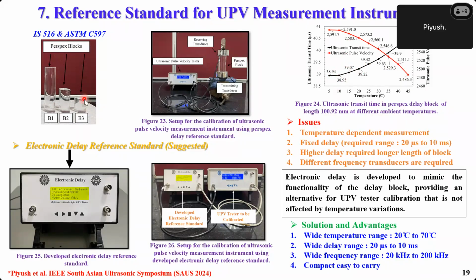Also, this small one, B3, is only for the 25 microsecond measurement, but the standard says we require blocks from 20 microseconds to 10 milliseconds. And this big one, B1, is about 100 mm in length. So it's a very big sample only for the 100 microsecond. So you can imagine how big a block we would require for 10 milliseconds, which is practically not even possible. And we also require a different frequency transducer for the measurement of ultrasonic pulse velocity in the different categories of concrete as per Indian Standard 516 and ASTM C597.